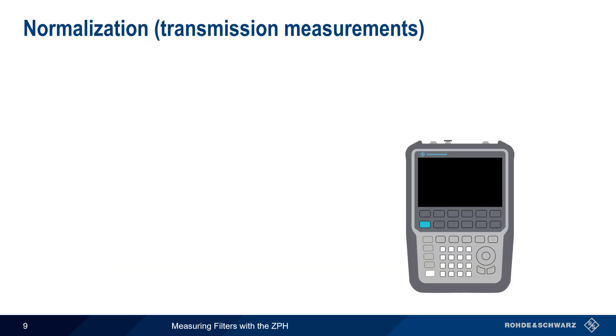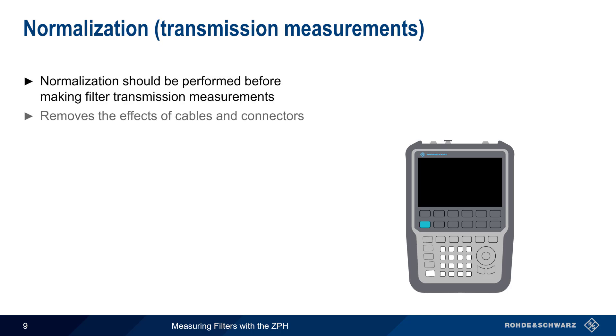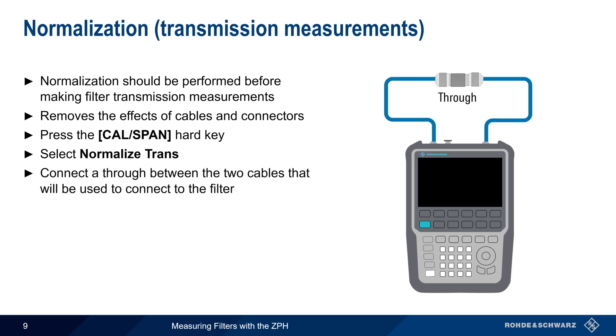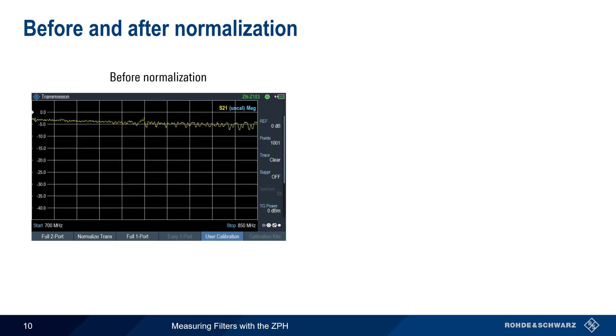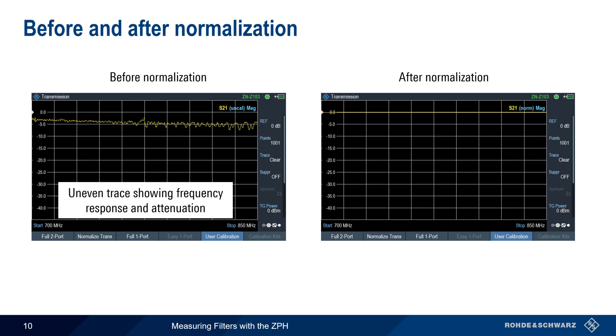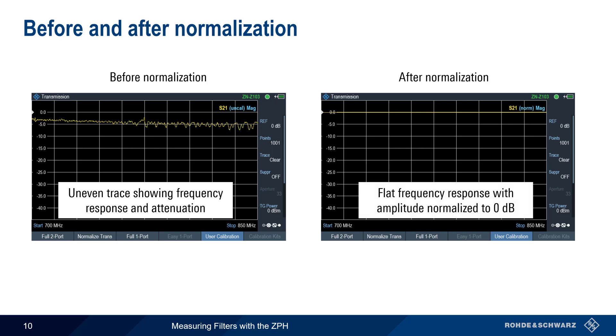A very important prerequisite to any transmission measurement is normalization. Normalization can remove or reduce the effects of cables and connectors on the measurements. To run normalization, press the Cal Span hard key and then Normalize Transmission. A through should be connected where the filter will be attached. After pressing Continue, normalization will complete in just a few seconds. Here is a typical display before normalization — although the tracking generator output is constant, the frequency response and attenuation of the cables will create an uneven or wavy trace. After normalization has been run, the line should be flat and normalized to 0 dB. All filter transmission measurements will now be relative to this level.